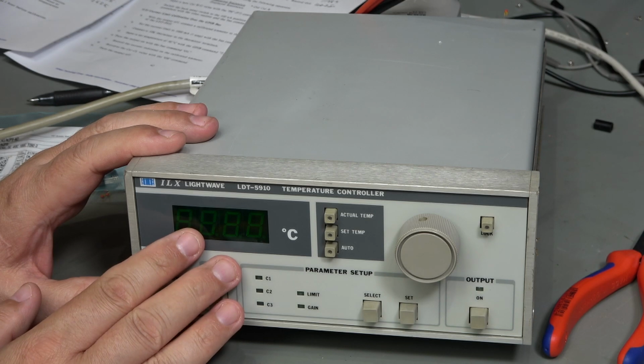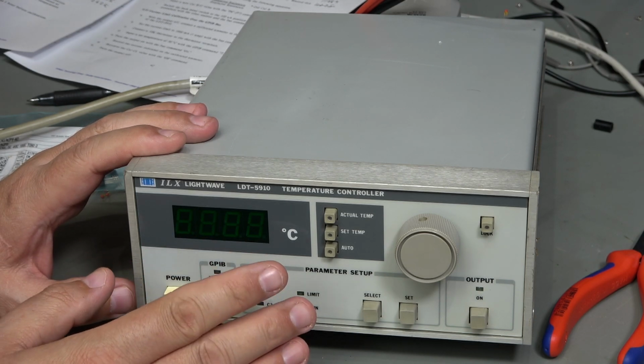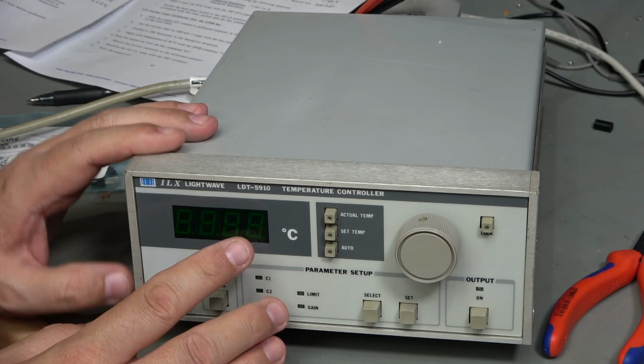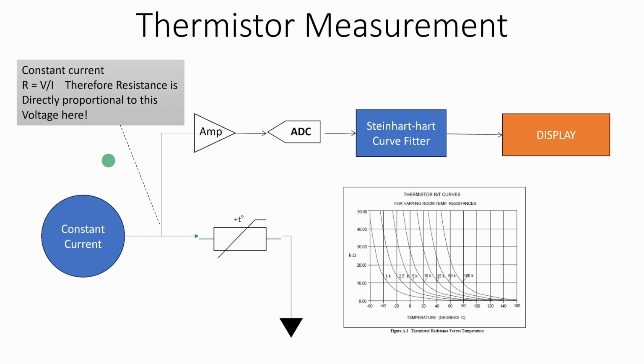My suspicions relate to, I suppose, the constant current supply maybe. Well, we can have a look at the constant current supply. I thought it'd be a good idea just to have a quick understanding of the principles at work here. So we've got a thermistor connected to the back of our unit, and we want to measure its resistance. The reason we want to do that is because the resistance is proportionate to the temperature. Unfortunately, it is not a linear relationship, but to measure our resistance, we can use Ohm's law. The easiest way is that we output a constant current and we pass that through our resistor to ground. That simple, really. Now, this point here, where the constant current goes into the resistor, has a voltage, and the voltage is of course directly proportionate to whatever that resistance is, because the current is constant. So all we've got to do is measure that voltage, and then we can do the calculation resistance equals voltage divided by current. We know current because it's constant, and that's our lot.